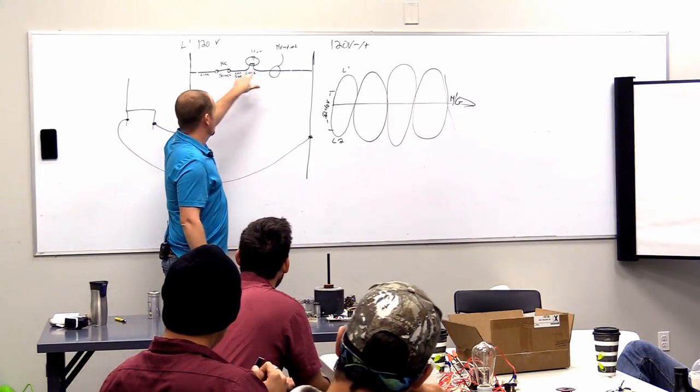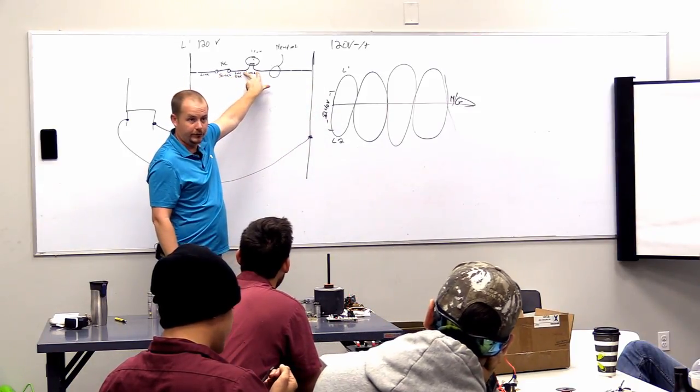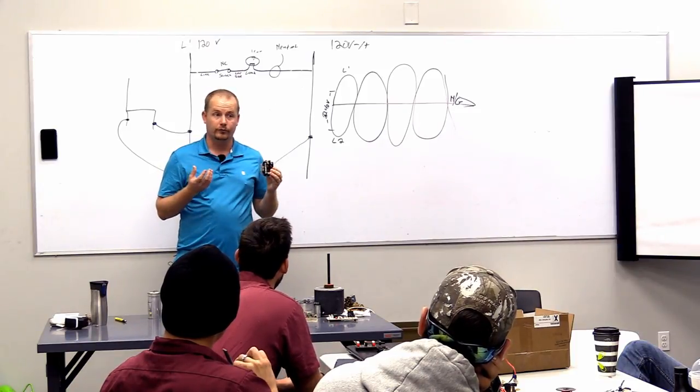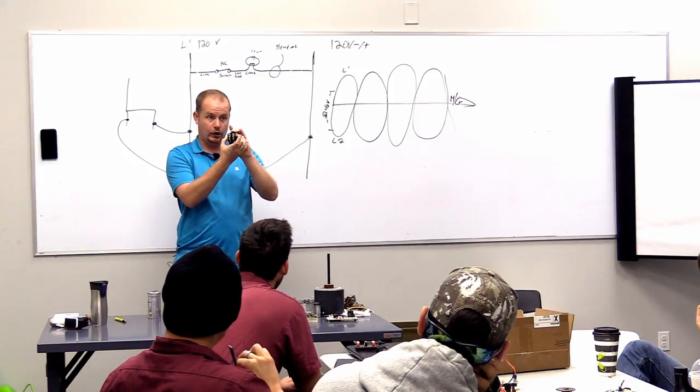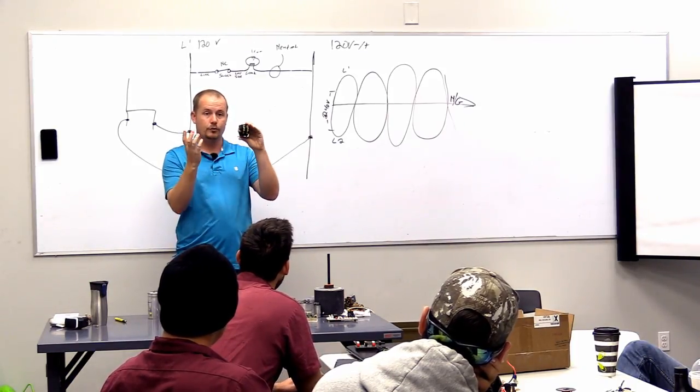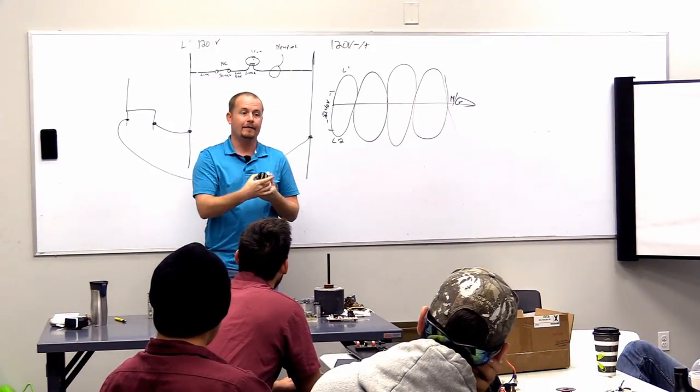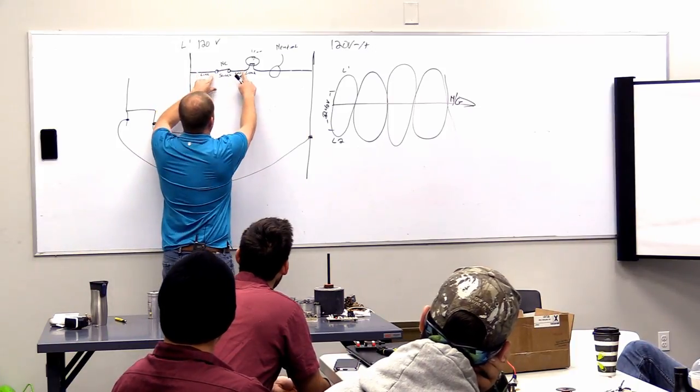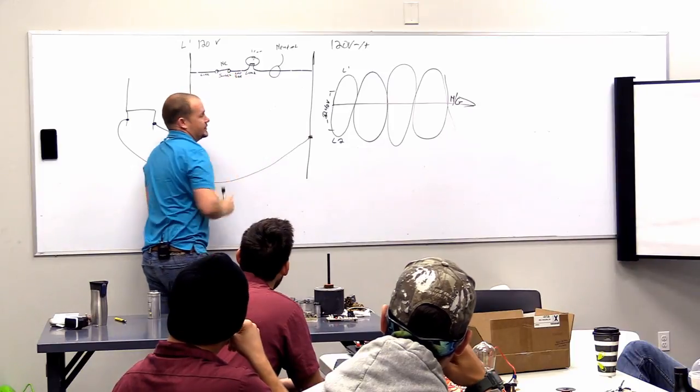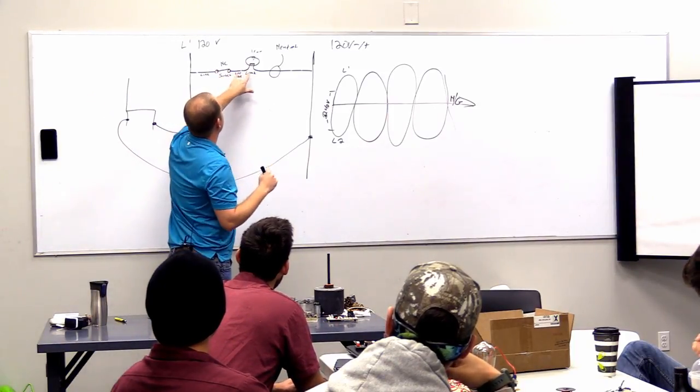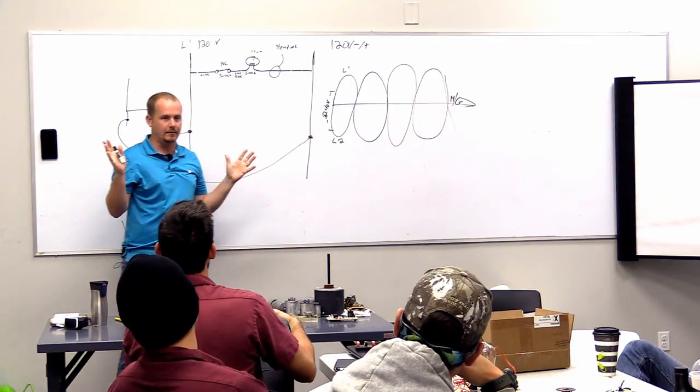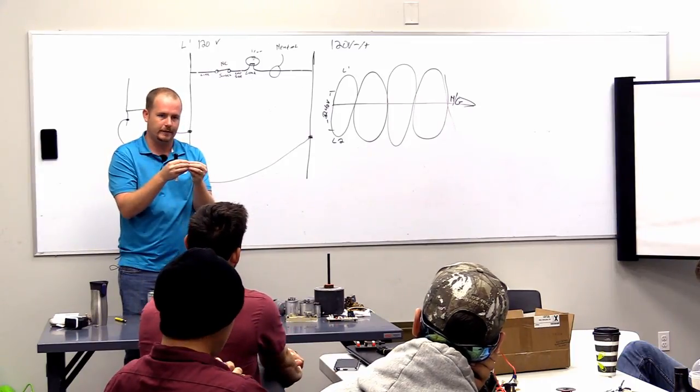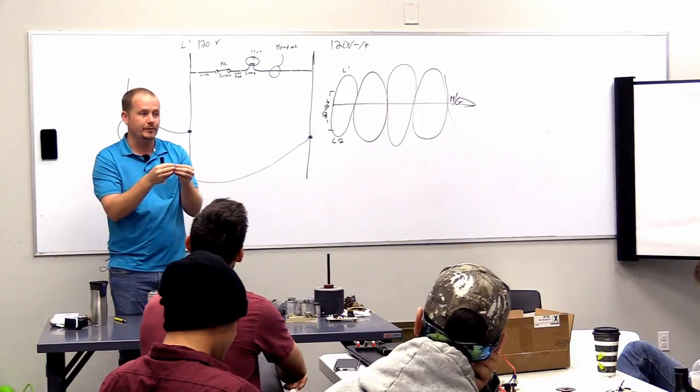And when we read across the load, when the circuit is energized, that's when we read our applied voltage across the load. Which is why if I ask you does the contactor have 24 volts? What I'm asking you is on the coil of the contactor, that's the load, that's the part that does work of pulling the contactor in, it's an electromagnet. Do we have 24 volts applied across the load? If you take the line going into the contactor and just like with the light, you read in between any two points that are electrically the same, you're going to read nothing, no matter whether this switch is open or closed. If I read in the two electrical points that are exactly the same, you're going to read zero. And it doesn't matter if there's electrical potential there or not. Because remember potential, it's another word for voltage, that just means there's the potential to do work. There's a charge that exists there, but it doesn't mean that it's actually doing anything.